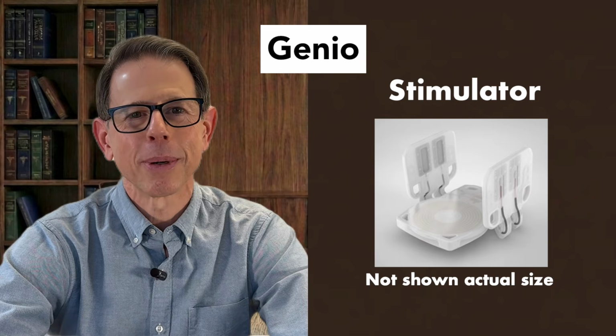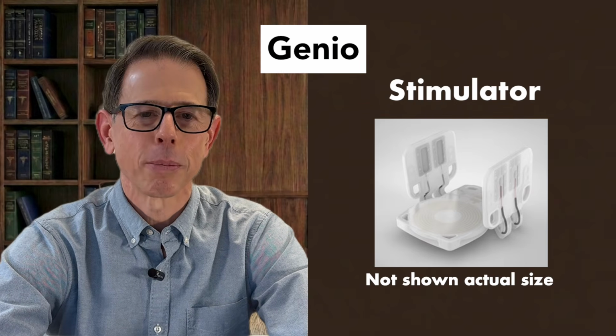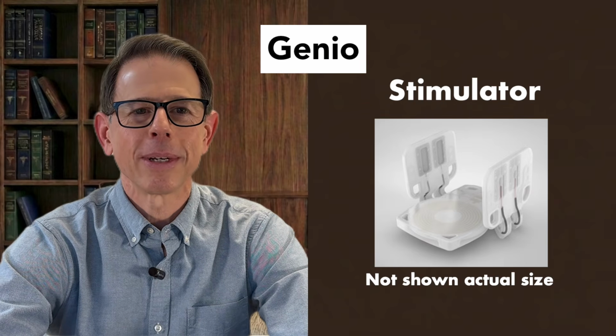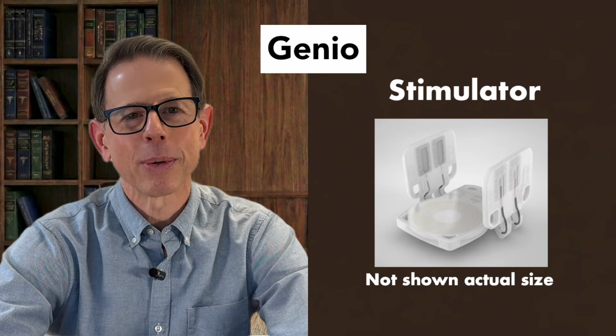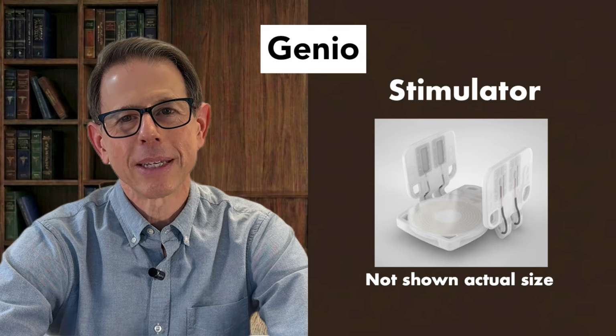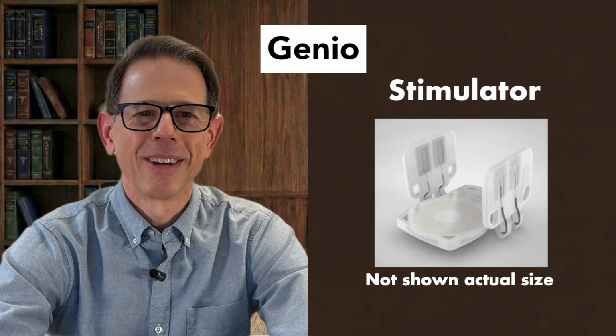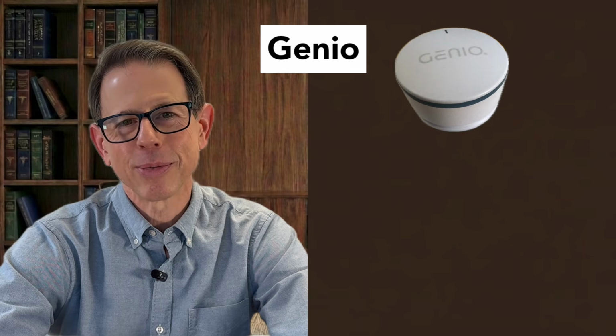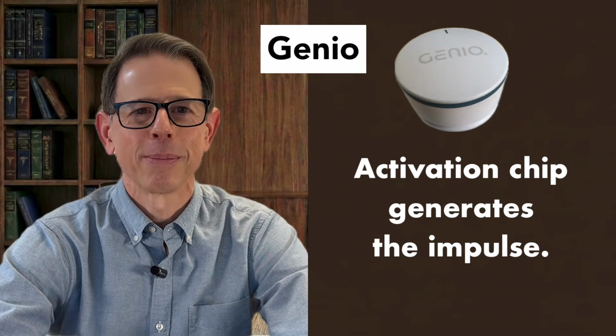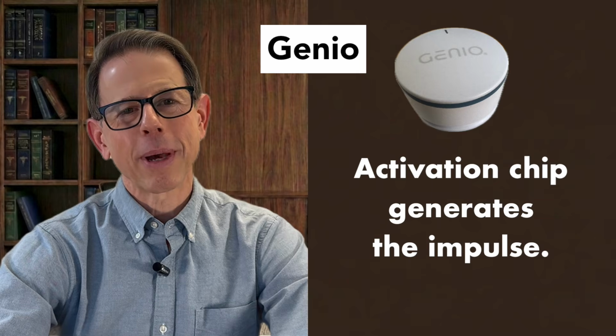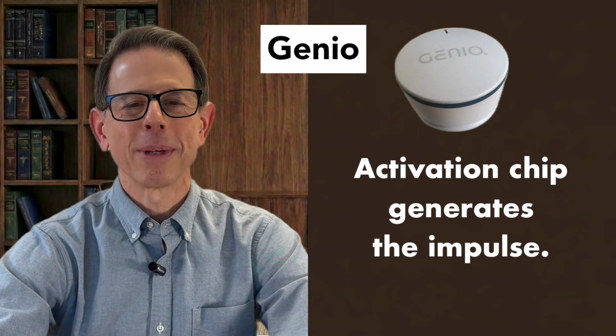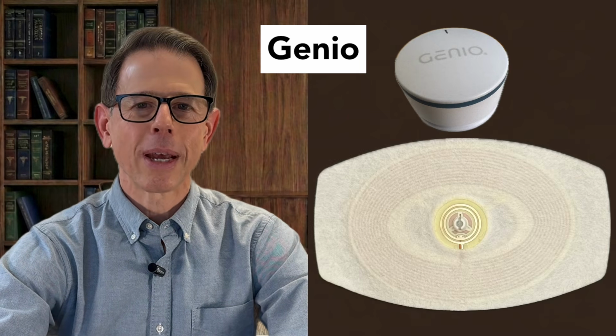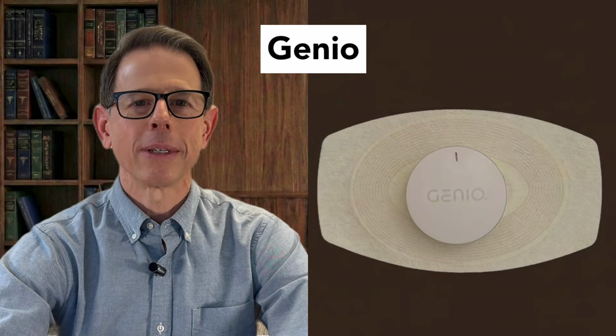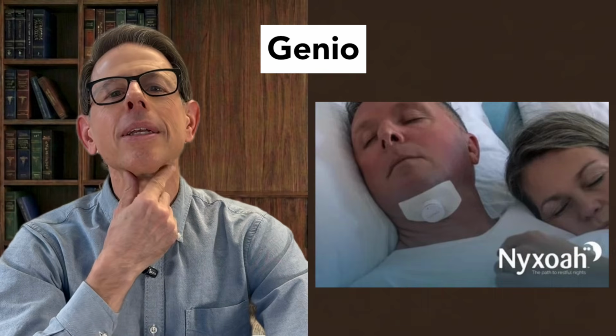Genio is a hybrid system. There is only one implanted component, a stimulator with two electrode paddles. The stimulator is about 1 inch long and about 3/4 of an inch wide. It's as thick as 2 quarters stacked together. The impulse generator for Genio is referred to as the activation chip. The activation chip and its battery are worn externally rather than being implanted. The chip is attached to an adhesive patch that is placed on the skin just below the chin each night.